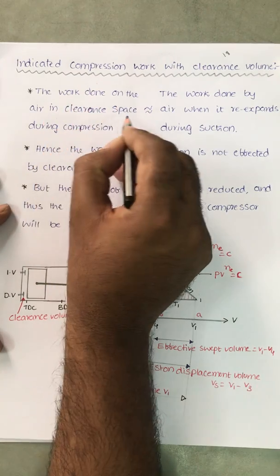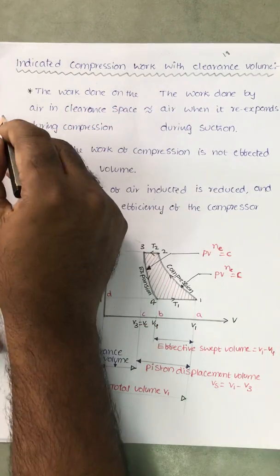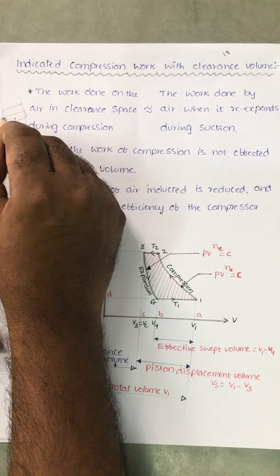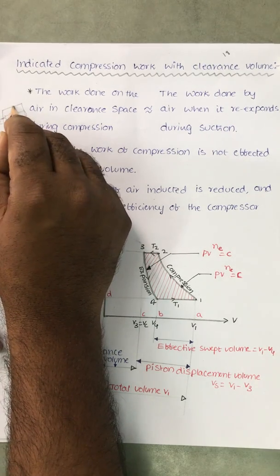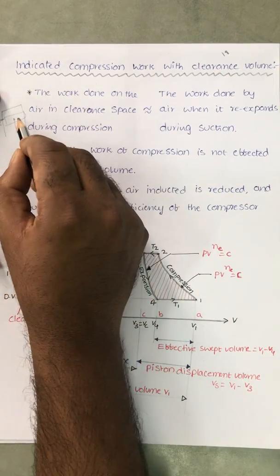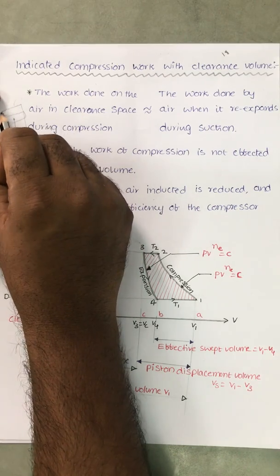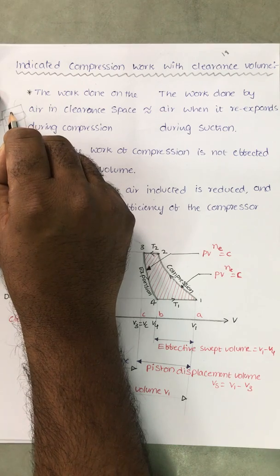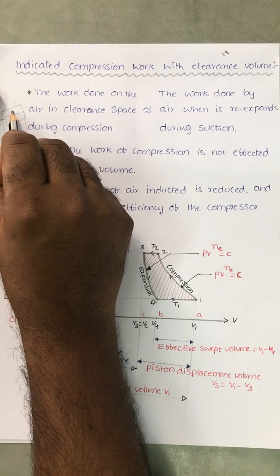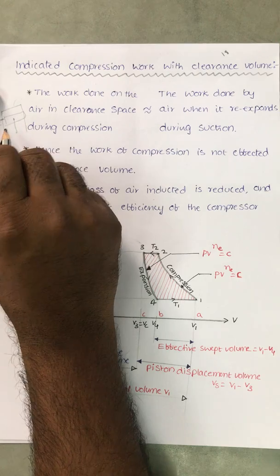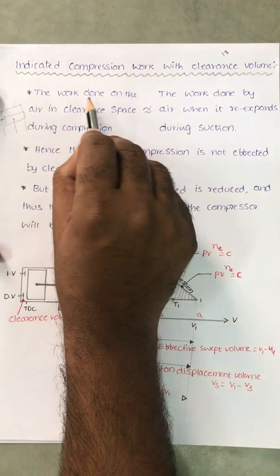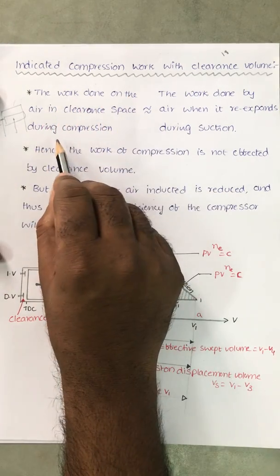The work done on the air in the clearance space during compression — consider the piston-cylinder arrangement. At the top dead center (TDC), when the piston reaches TDC, some amount of volume is present at the top of the piston; that is called clearance volume. So if we compress the air and deliver it, some amount of air remains inside the clearance volume, which affects the next suction stroke, because this air will expand first before fresh air can enter.